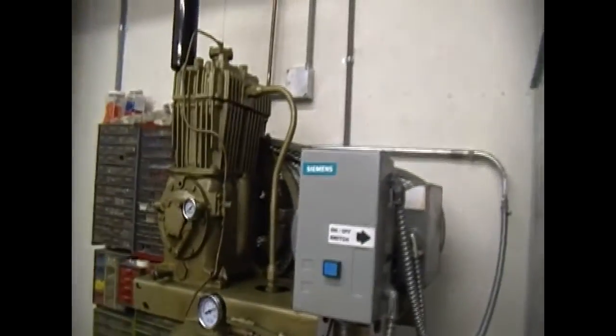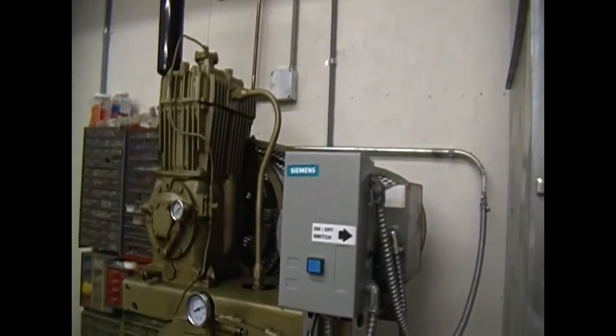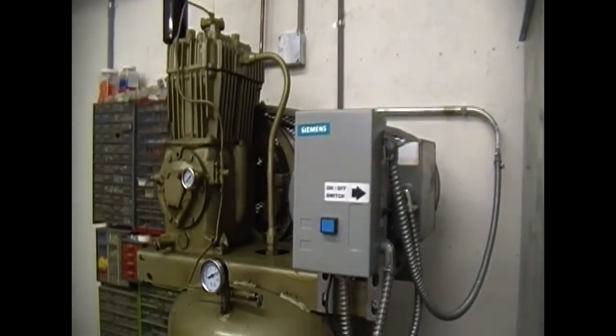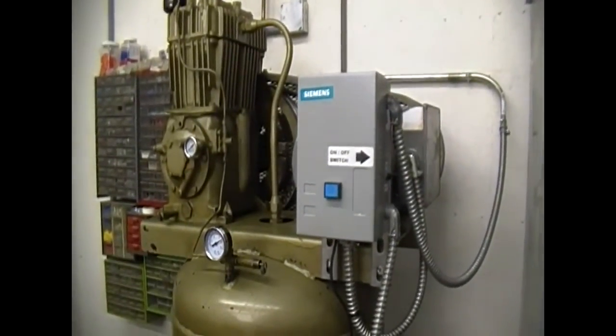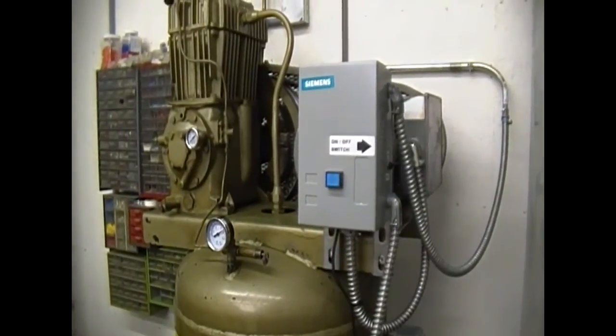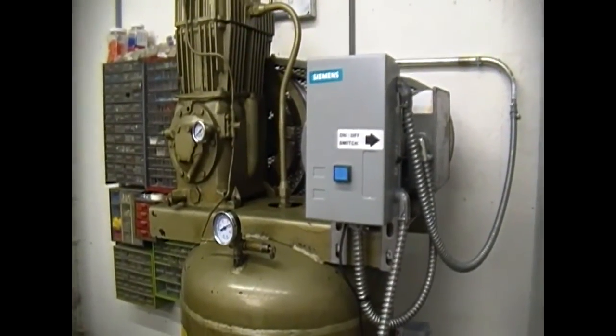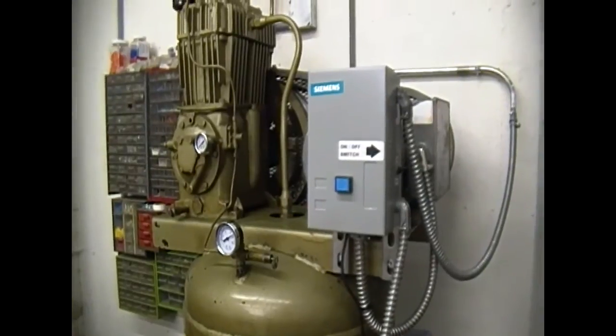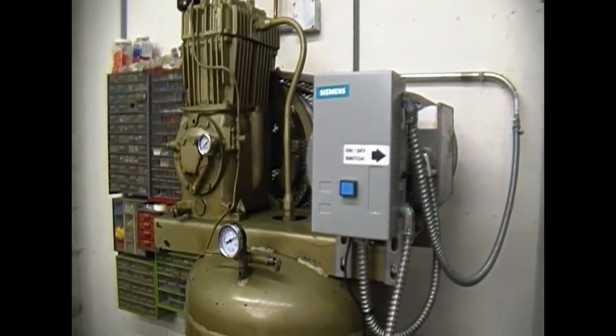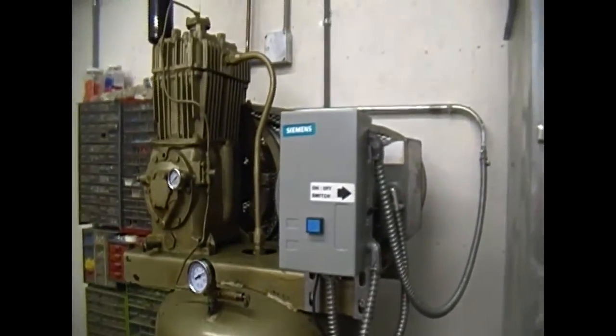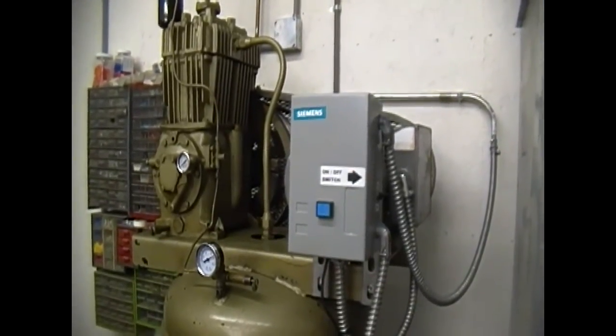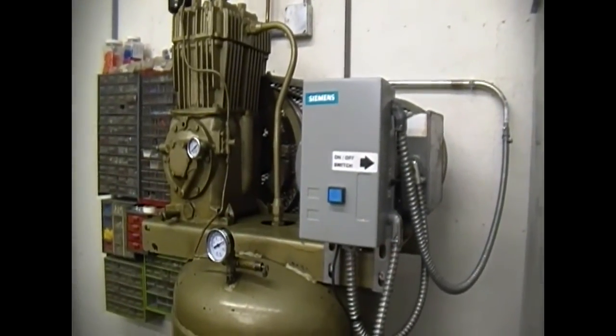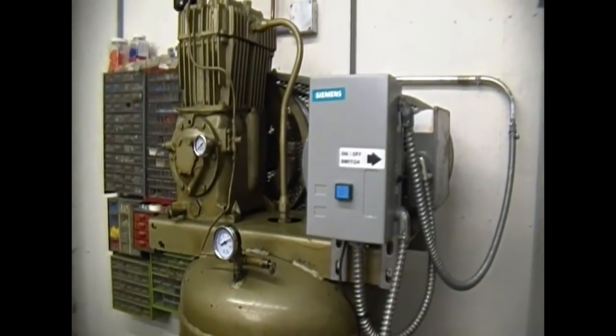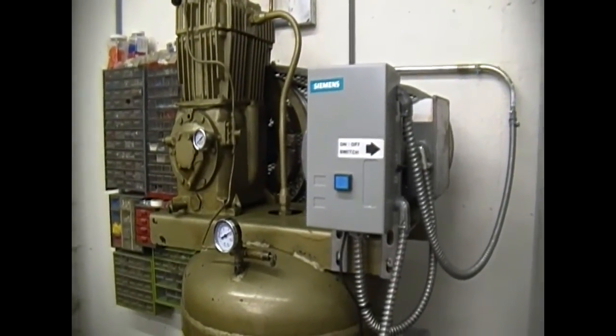So like I said, I've checked the inrush current on startup, and it's about 112 amps on each leg roughly. So I'll go and check all the connections here, hopefully this weekend or before, especially on that leg. Maybe I do have a loose lug on the circuit breaker or on the disconnect in here, or maybe on the contactor itself. Who knows? But like I said, it just started doing it within the last, I'd say, month or month and a half. So, all right, thanks for watching.